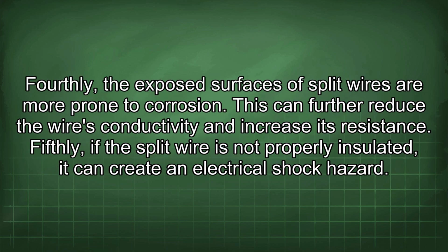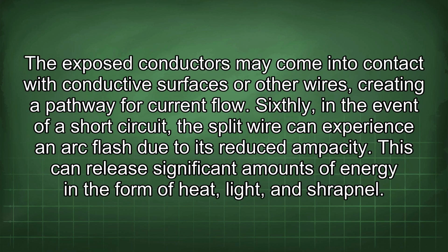Fourthly, the exposed surfaces of split wires are more prone to corrosion. This can further reduce the wire's conductivity and increase resistance. Fifthly, if the split wire is not properly insulated, it can create an electrical shock hazard. The exposed conductors may come into contact with conductive surfaces or other wires, creating a pathway for current flow. Sixthly, in the event of a short circuit, the split wire can experience an arc flash due to its reduced ampacity. This can release significant amounts of energy in the form of heat, light, and shrapnel.